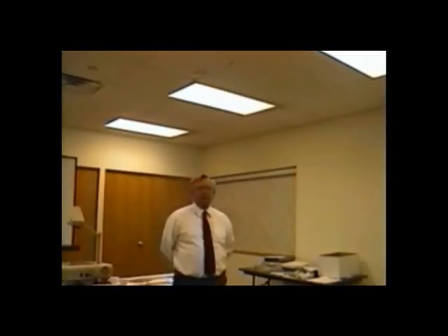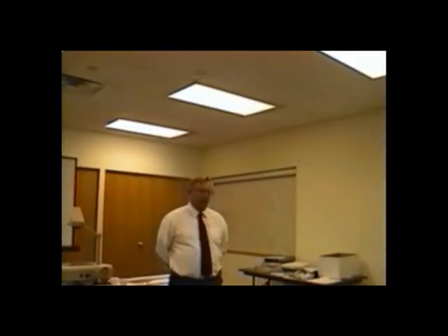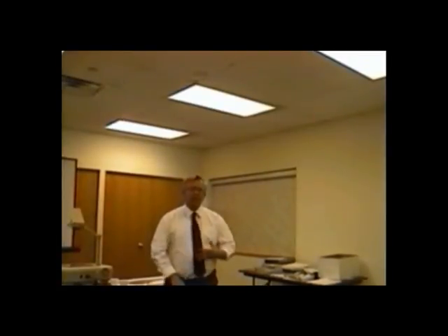Let's talk about that real quick, please. We only tell you to use a low side dryer today. If you have a burnout, you do not install a low side dryer for any other reason. However, for the past 2 years, we don't even tell you to do that anymore. Since R-11 has not been available, we could not flush anything out anymore.